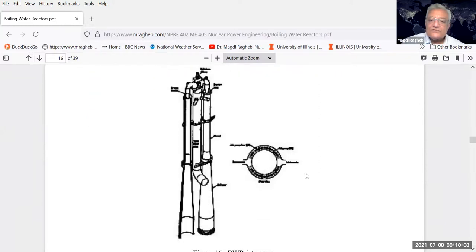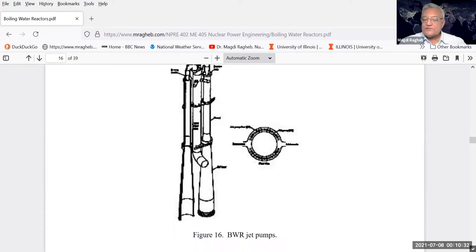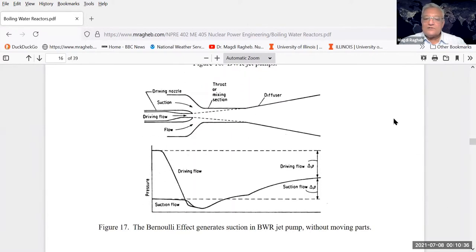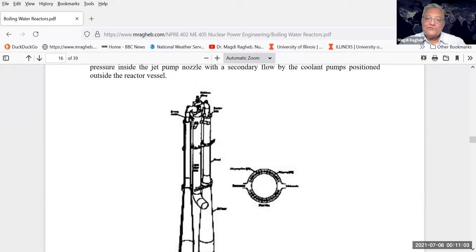The jet pumps are used inside existing reactor designs. The pumps are driven from outside the pressure vessel but the flow nozzle is inside the reactor pressure vessel itself. It's called a jet pump because you bring in a driving flow from the outside: inject water at high pressure through a nozzle with an opening, creating suction that circulates water inside the pressure vessel without having the pump itself inside. There have been problems with those pumps, so they have been replaced in the latest designs with what's called canned rotor pumps.